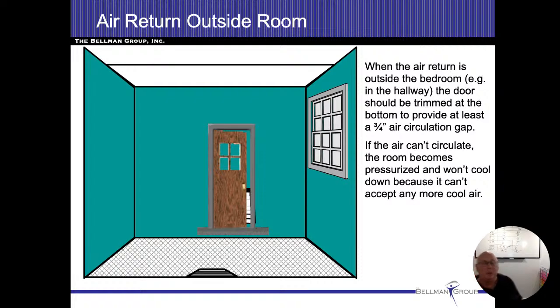All right, typically if they're going to use the gap under the door, we should have about 3/4 of an inch on the underside. Me personally, I like it when they put vents up over the door, or at least on the side of it, so they let the air flow through that way. I know that doesn't help much with sound, but if you don't let the air out of the room, then we can't let more air into the room. Sometimes you'll have that 3/4 inch gap under the door, but then the people moving in are going to end up putting carpeting down.